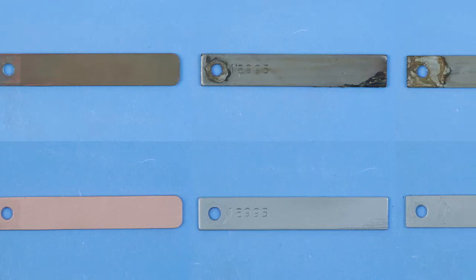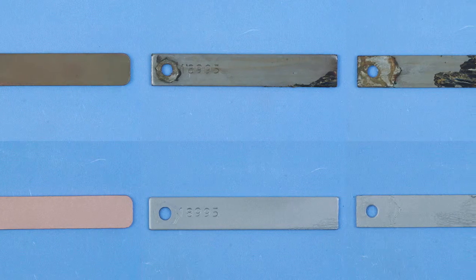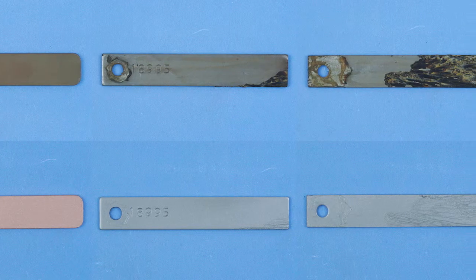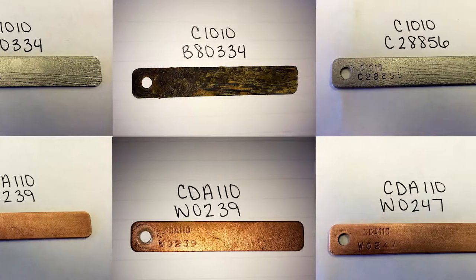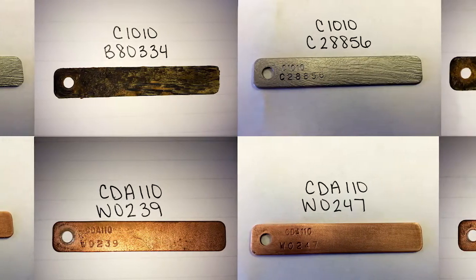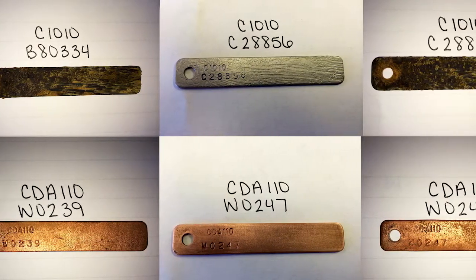We also measure another important area: the corrosion that may be occurring in the cooling water system. So we use regular mild steel corrosion coupons for that evaluation, as well as copper corrosion coupons, since there are copper components within the cooling water system.